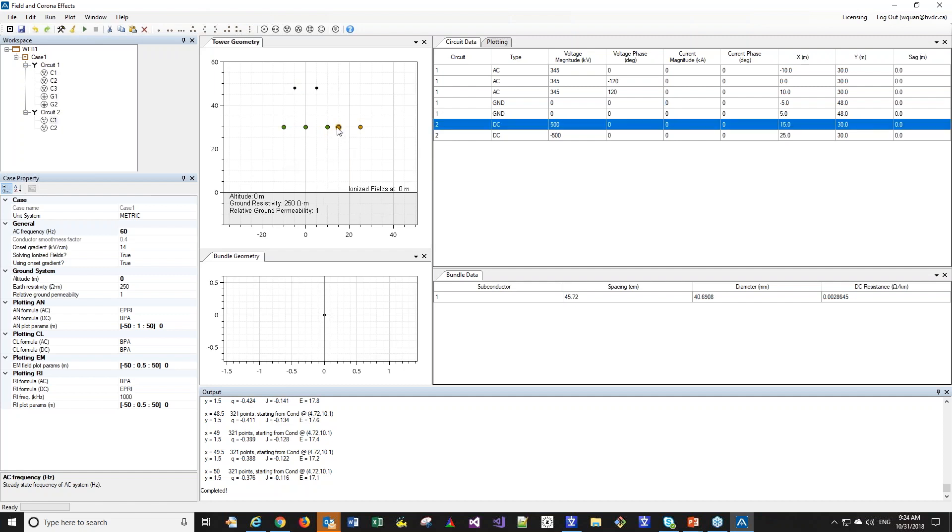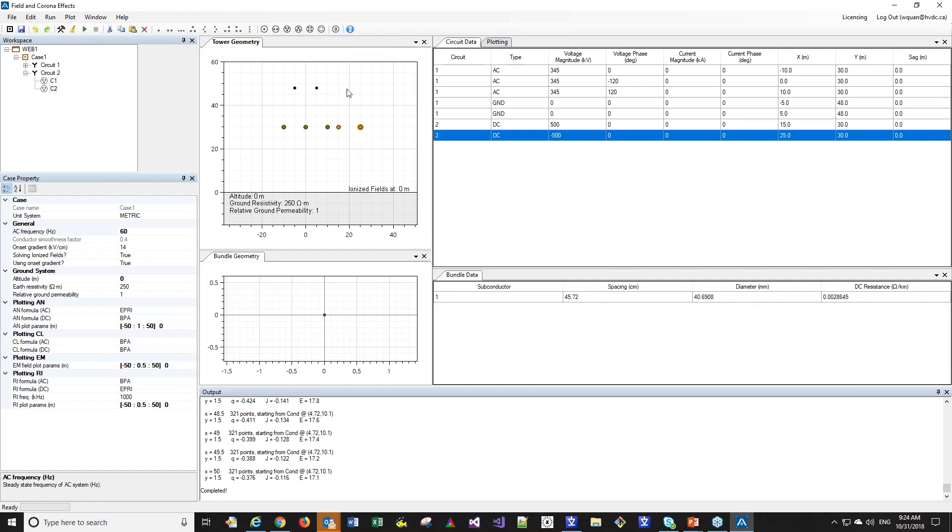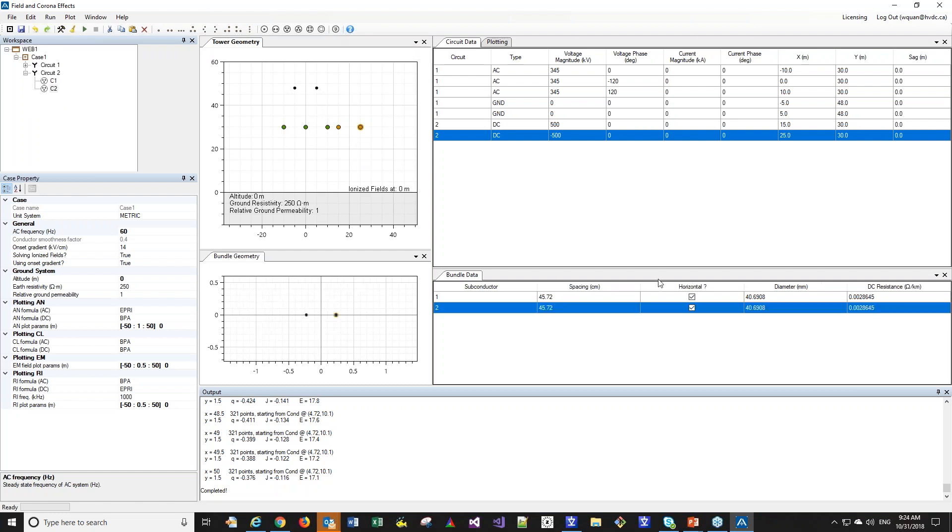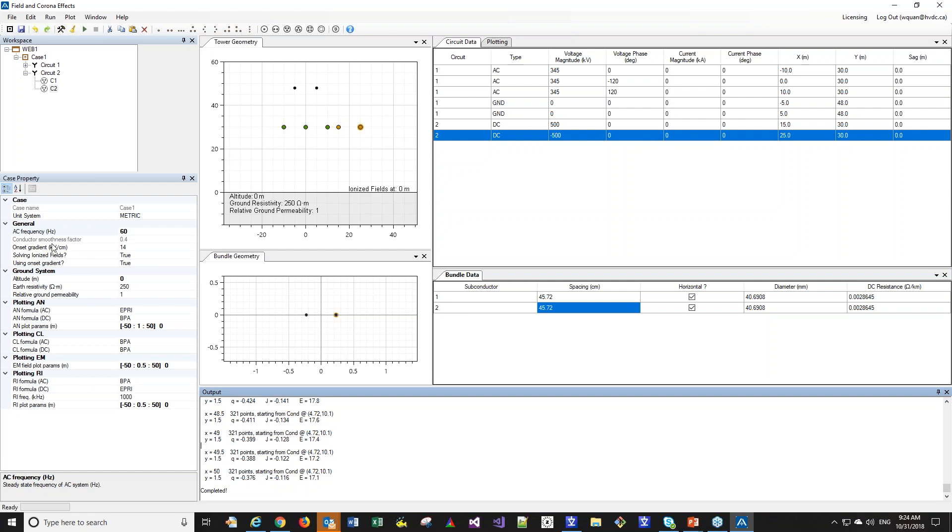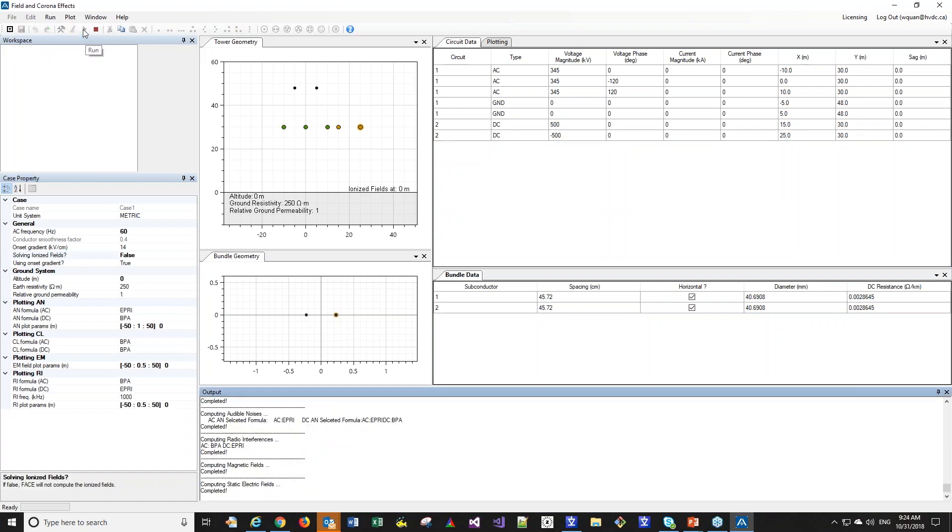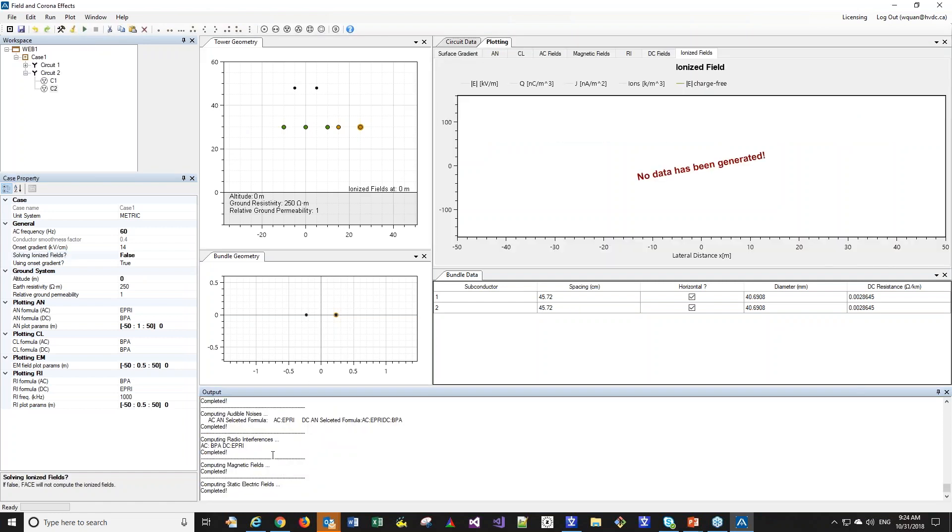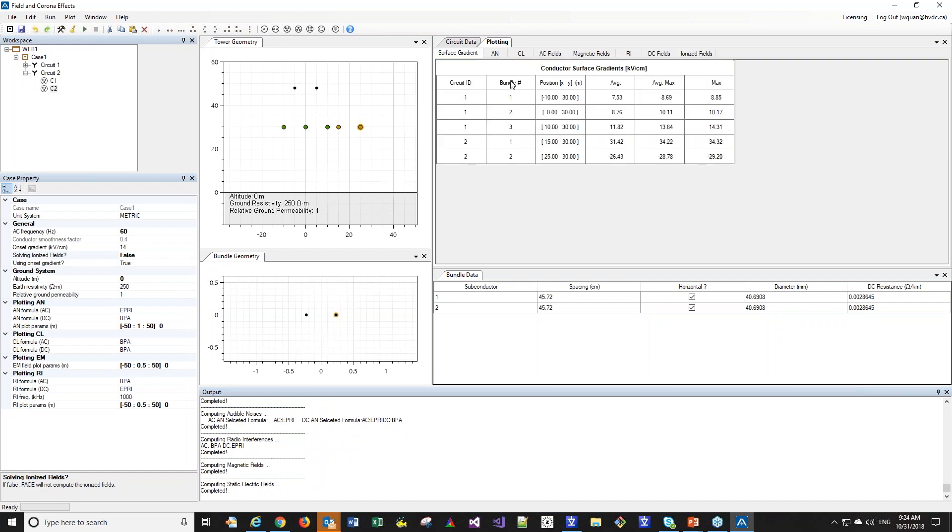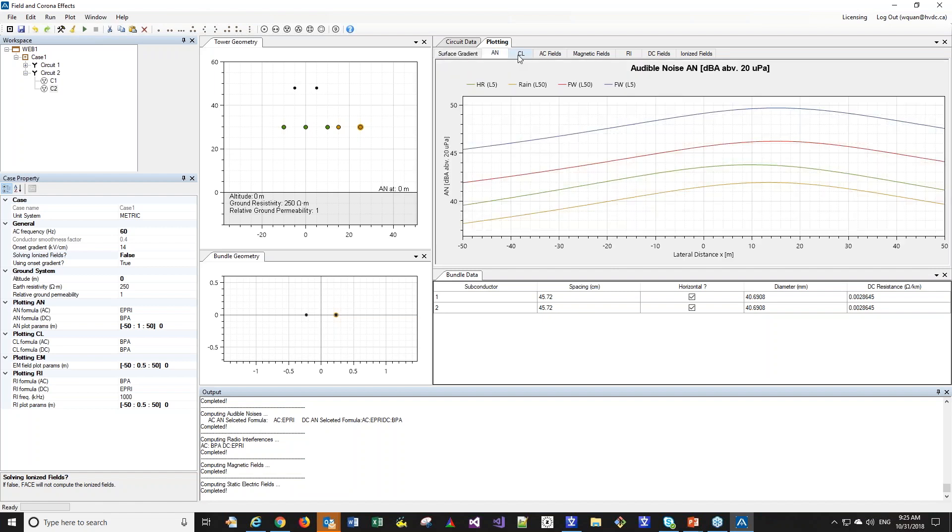That's our AC system. Let's create a DC system of just two conductors with no ground conductors. We can see that right now it's set as DC. Let's go DC 500 and place that onto our system. However, let's change the orientation slightly. Let's move the DC system to the right by 20 meters. We can pick the first conductor and move it in the X. Let's change that to 15 here and change here to 25. Now we have the two AC and DC systems. We can do the similar thing with the bundles for the DC. Let's create it as a two-conductor bundle. We can add another bundle here and another one. You can see we can always set the spacing right here for the bundle.